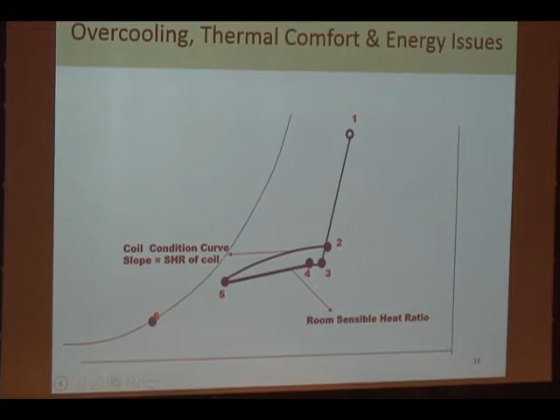The outside condition in Singapore, very hot and humid, or any hot and humid climate, and we'd like the space to be at this condition, point 4. This is what you see in front of the cooling coil in the air handling unit, where air comes out at a certain condition into the room, and this is a continuous process. If everything is fine, that's what the designer estimated. Now, what happens if we have an oversized coil?